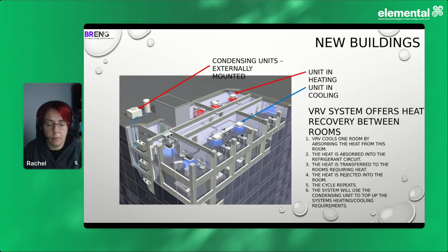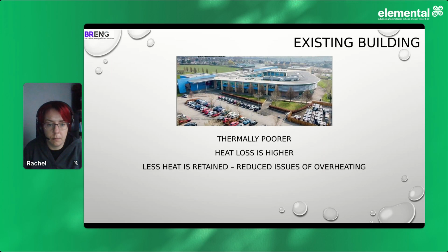So what we suggest is, if you put a VRF air conditioning system in, you don't use it to cool, you use it to heat, but use it to harvest energy at certain times of the year from the warm parts of the school and use it in the colder parts of the school. And that reduces your energy consumption considerably. The challenge now is faced in existing buildings. Now these are generally thermally poorer. The heat loss is obviously higher and less heat is retained, but that also is a benefit because it reduces the issues of overheating.